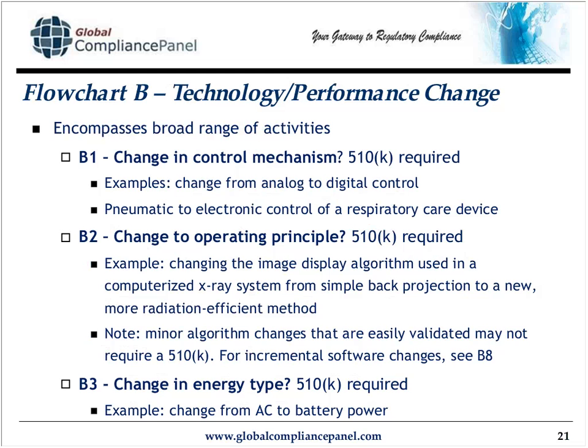Any minor algorithm changes, code changes that are easily validated via software validation might not require a 510K. We'll take a look at decision B8 when we get there. And a change in energy type, yes, a 510K is required if I'm changing from AC mains to battery power, or vice versa.